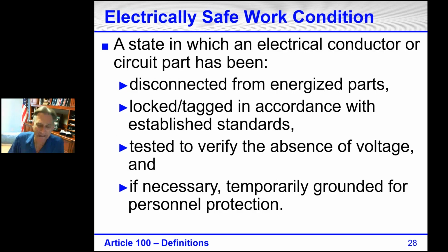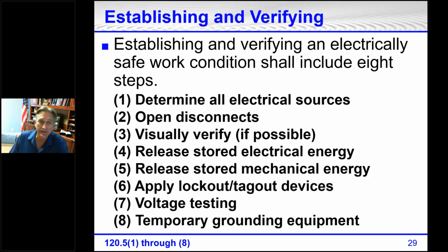Electrically safe work condition is a defined term. It is a state in which electrical conductors and circuit parts have been disconnected from energized parts, locked and tagged in accordance with established standards, tested to verify the absence of voltage and, if necessary, temporarily grounded for personnel protection. There are 8 steps in establishing and verifying that equipment is in an electrically safe work condition.